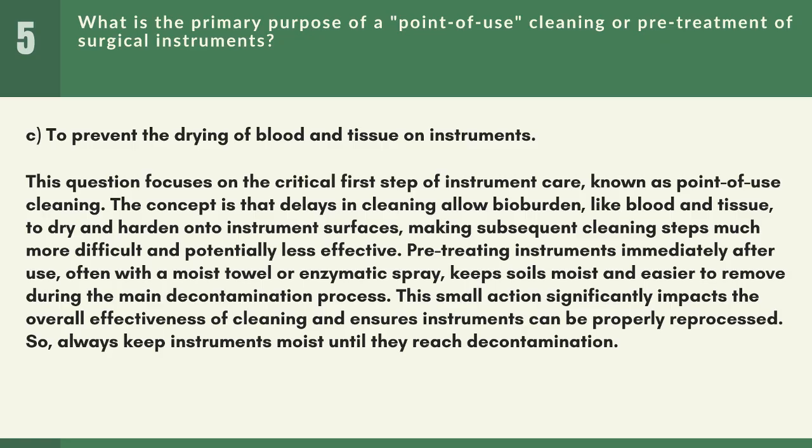Pre-treating instruments immediately after use, often with a moist towel or enzymatic spray, keeps soils moist and easier to remove during the main decontamination process. This small action significantly impacts the overall effectiveness of cleaning and ensures instruments can be properly reprocessed. So, always keep instruments moist until they reach decontamination.